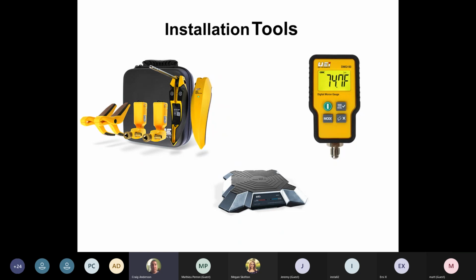If the unit is running outside and you're playing with airflows inside to see what's going on, to raise your low side or whatever you're doing, checking filters, you could be inside looking at your phone instead of going outside. Okay, let's go outside and see what that unit's doing now. Great investment if that's something that you like, the techie stuff. If you're getting into the trade and you're planning on staying in the trade, a great add-on to your toolbox. And that's through UEI. It's called the Hub 6.